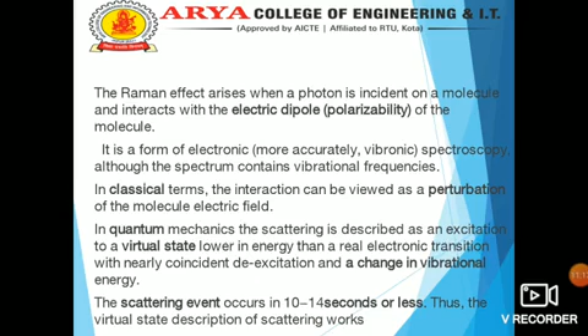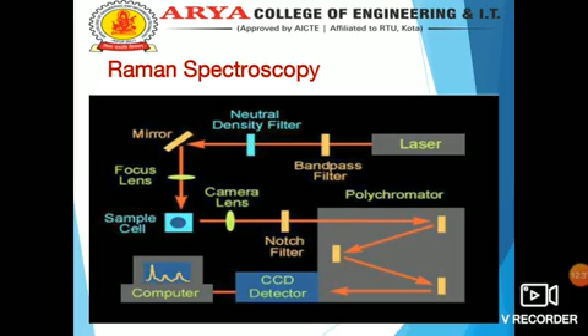And this is the diagram of Raman spectroscopy, in which the beam from the laser comes to the mirror through a bandpass filter and the neutral density filter, and this signal comes to the sample cell through the focus lens. Then this signal comes to the polychromator through the lenses and filters, and after that this signal is detected by the CCD detector, and we can see the graph or plot in the computer.